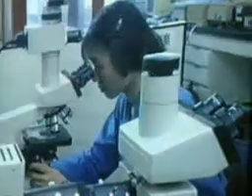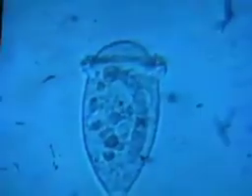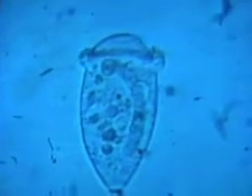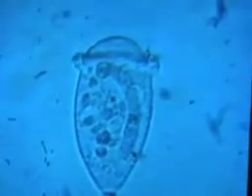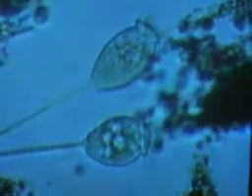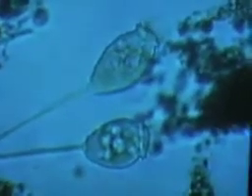Let's take a closer look. A flock resembling brown-colored mud. This is activated sludge. This activated sludge is made up of many different types of protozoa, bacteria, and other organisms. These microorganisms feed on the waste and the sanitary sewage as nutrients and grow into large flocks which easily sink.